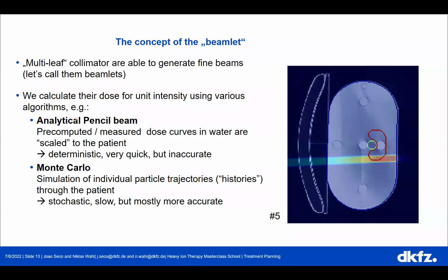So what is the advantage of the beamlets? Now we can compute those calculations for tiny little beamlets all together. So we can do what is called pencil beam planning through an algorithm, or we can even generate the beamlets through Monte Carlo, although this is extremely slow, and so there are various variance reduction techniques to do this faster. Right, so the key point with the beamlets is we have the power to simulate and modulate our beam intensity.